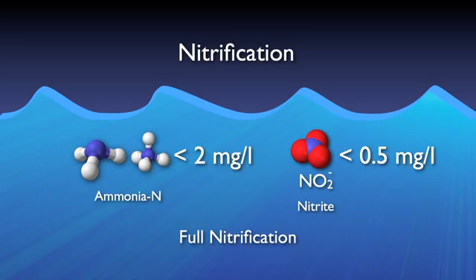As a comparison, in order to remove 1 pound of BOD, 1.2 pounds of oxygen are required. However, to reduce 1 pound of ammonia to nitrate, 4.6 pounds of oxygen are required. Since getting dissolved oxygen into wastewater is a very energy-intensive process, it would benefit every treatment plant's electrical bill if they didn't aerate more than they needed to. Over-aerating does nothing to improve the process, it really is flushing money down the toilet.